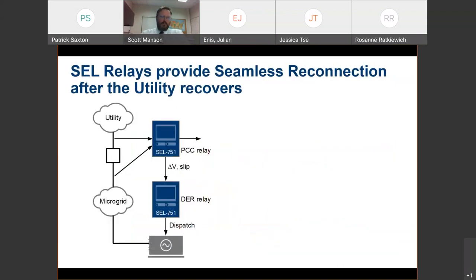Here's another example. Actually, the same job. You have a utility with a microgrid, and you have a protective relay, a 751. That's a typical model that my teams use at the point of common coupling, called the PCC. In this case, you have an islanded microgrid. The breaker is open. The breaker is the box. And perhaps this is a power shutdown of your local utility. You've got your microgrid running, and you say, hey, I'd like to get back on the utility grid. It's time to reconnect. In engineer language, we call that a 25. 25 stands for resynchronization. It means put your manual stick shift in gear and get moving.